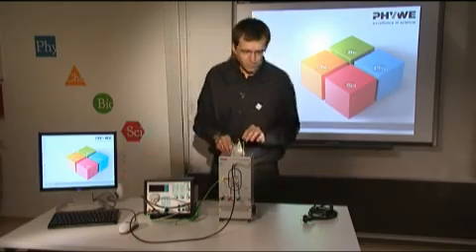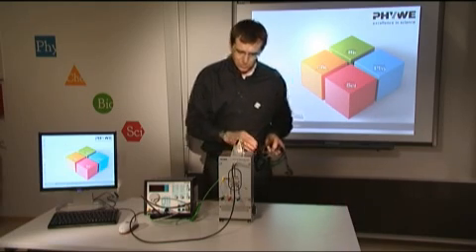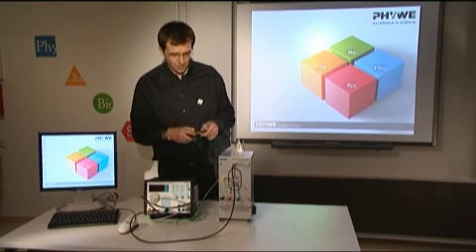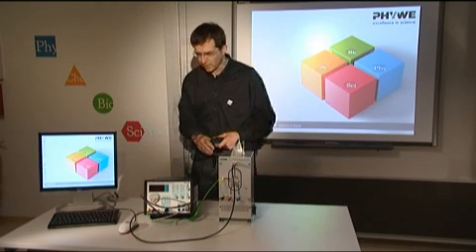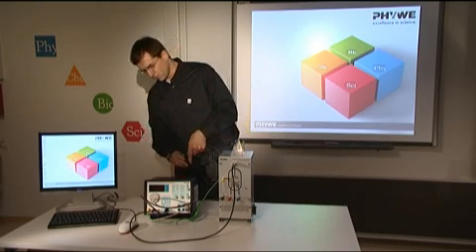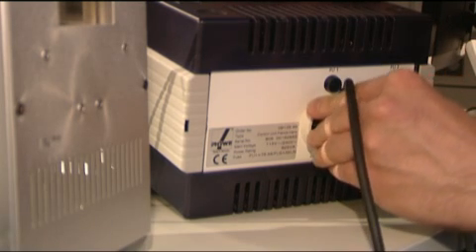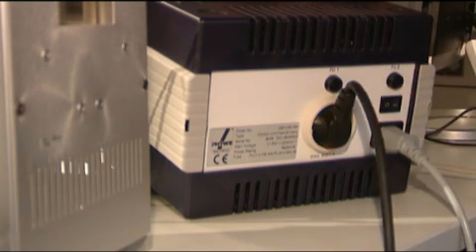This is just a temperature sensor. We also need to supply the tube with current to do the heating. There is a special plug at the back of the control unit that supplies the power for this, and it is connected to the tube.